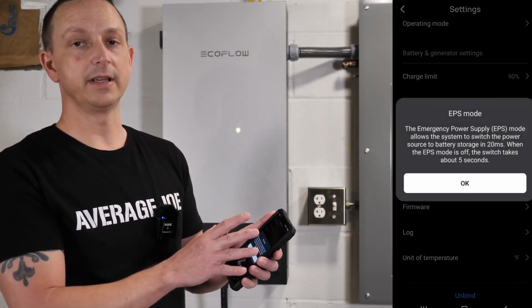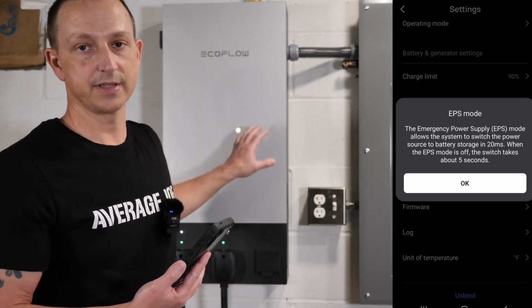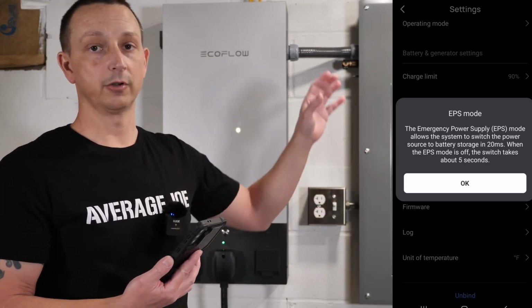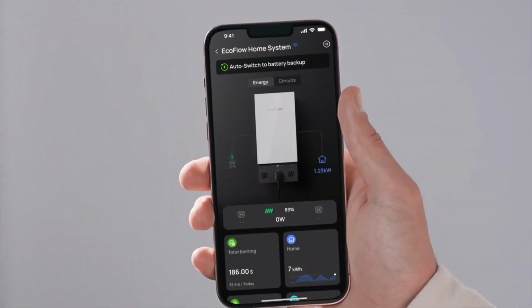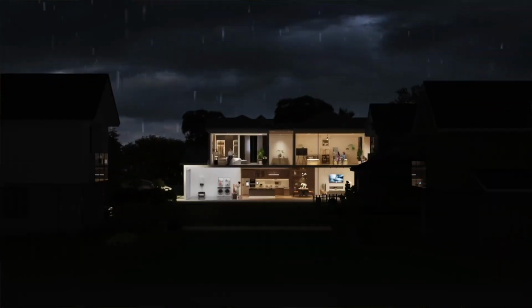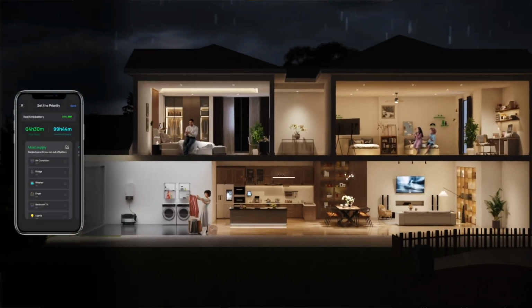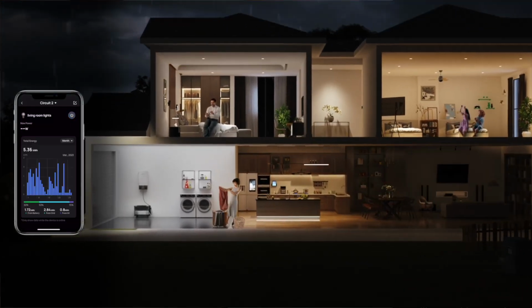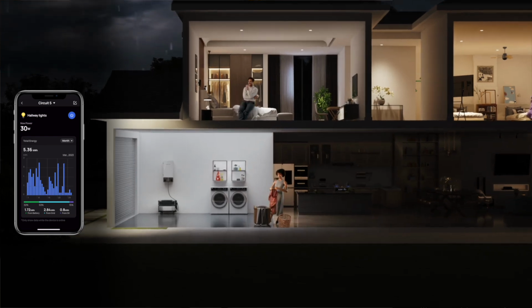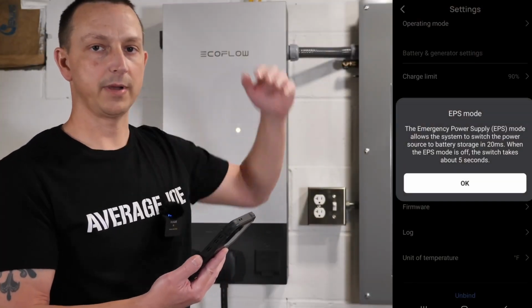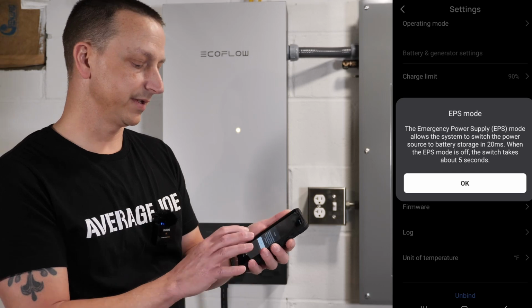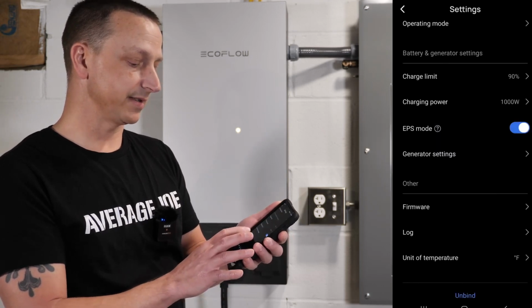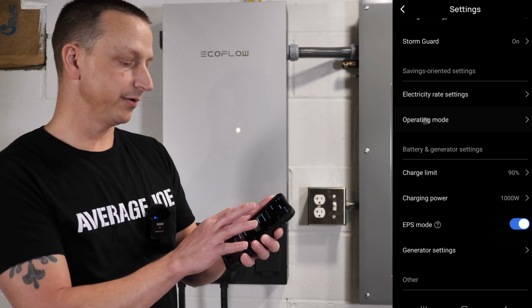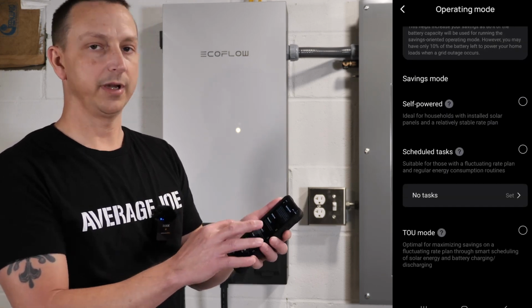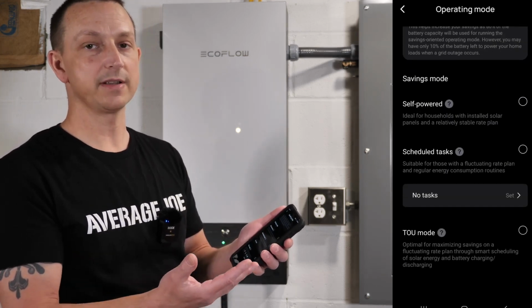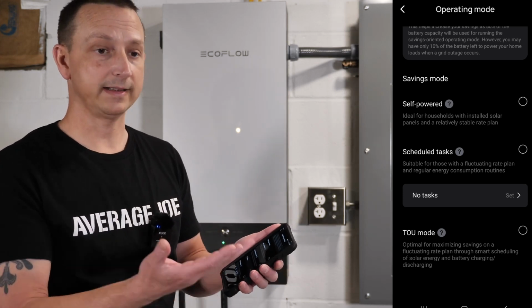If you have EPS mode enabled, you're basically using this system as a battery backup. So if the grid goes down, it automatically switches over and continues powering whatever you have connected within that 20 millisecond window. If you don't have this enabled, the system shuts down for up to 5 seconds like it shows here, then comes back on and continues powering your loads. This setting is actually disabled whenever you're using an operating mode up here, I'm pretty sure because you could already be off grid at that same time.